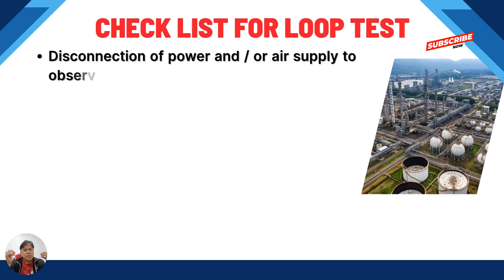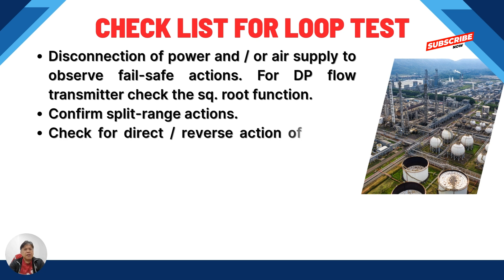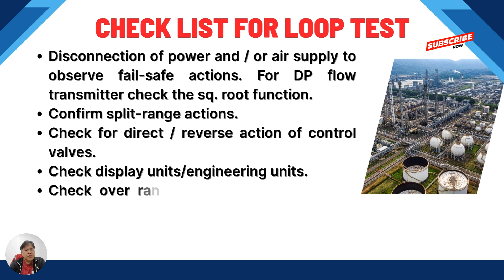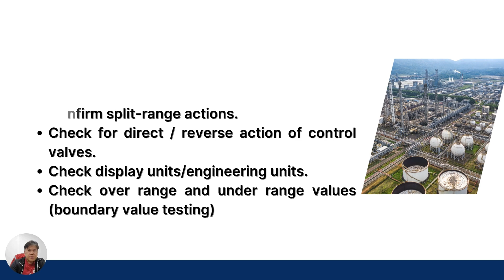So next, disconnection of power and air supply to observe fail-safe actions. DP flow transmitter check square root, confirm split range actions. Check for direct and reverse action of control valves. Check display unit engineering units. Check over range and under range value. So next slide. So check overrange and underrange values, boundary value testing.